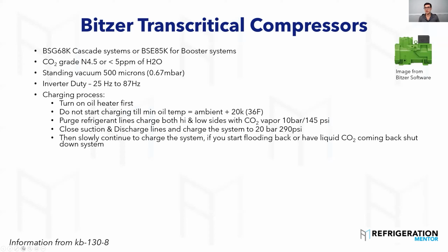Close the suction and discharge lines to the system. I've seen this here: when you're evacuating and pressure testing the system, they want you to close off that compressor, which totally makes sense. If you're pressure testing that system and you leave that compressor open, you could get moisture or air inside there. This should be standard anyway, but you should shut those suction and discharge valves. You don't want that. And slowly continue.